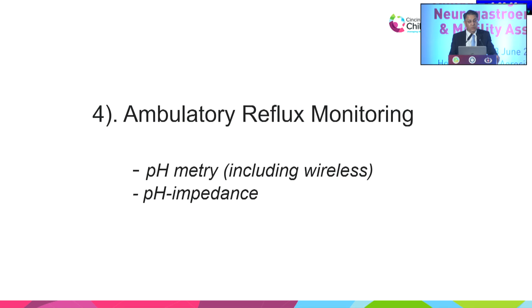Moving on to the main thrust of this talk, ambulatory pH monitoring. You could do pH metry, which includes the wireless Bravo system, or pH impedance. The pH metry is of two kinds, as I said. One is wireless, one is catheter based. The left is the traditional one that we have had for many decades. It has the catheter going into the esophagus with the pH sensor in there and the recorder. And on the right, you see the Bravo system, which is endoscopically placed. It's wireless, and it communicates wirelessly with a recorder that's worn by the patient.